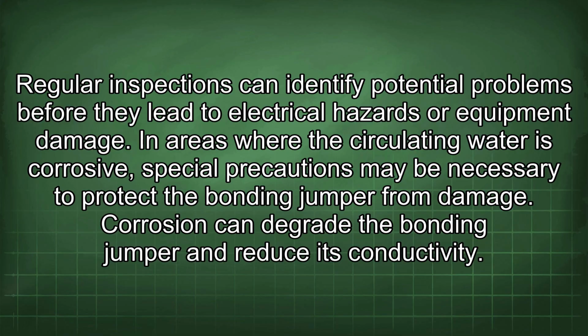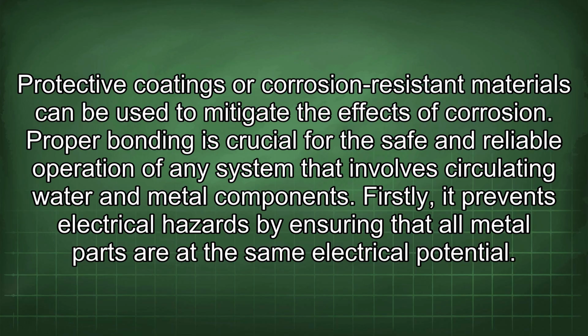In areas where the circulating water is corrosive, special precautions may be necessary to protect the bonding jumper from damage. Corrosion can degrade the bonding jumper and reduce its conductivity. Protective coatings or corrosion-resistant materials can be used to mitigate the effects of corrosion. Proper bonding is crucial for the safe and reliable operation of any system that involves circulating water or metal components.